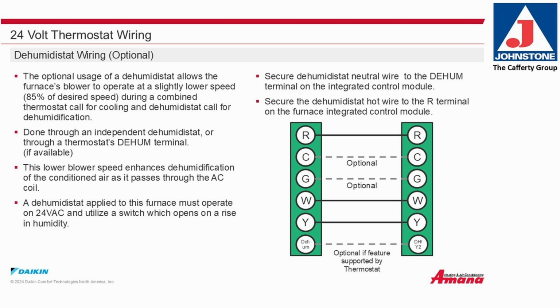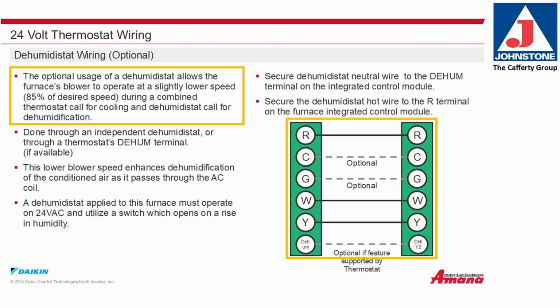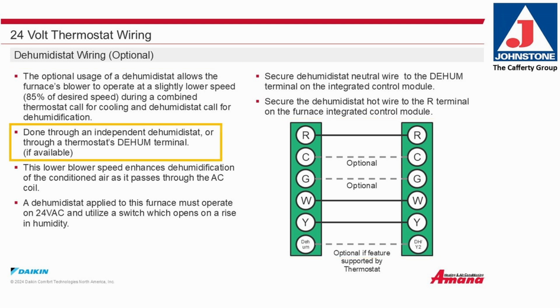24-volt thermostat wiring, optional dehumidistat wiring. The optional usage of a dehumidistat allows the furnace's blower to operate at a slightly lower speed, 85% of the desired speed, during a combined thermostat call for cooling and dehumidification call from the dehumidistat. This would be done through an independent dehumidistat or through the thermostat's dehumidification terminal if available. The lower speed of the blower enhances dehumidification of the conditioned air as it passes through the AC coil.